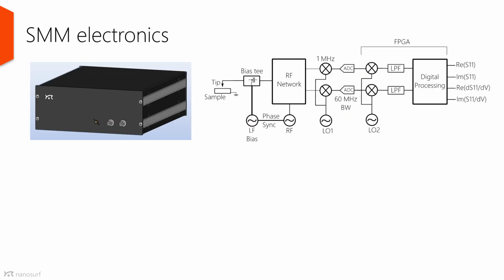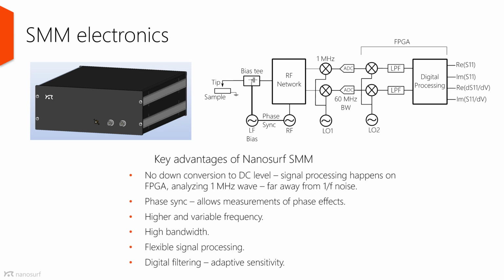For the SMM electronics, we have applied the many years of experience working with microwave technology and rethought the concept of the SMM hardware from the point of view of the lowest noise possible and the highest possible flexibility. We decided to use digital signal processing to work with 1 MHz signals without down conversion to DC level, to avoid 1/f noise. Our RF signal and the low frequency signal are phase synchronous, so you could study the phase effects better. We have a maximum frequency of 6 GHz, and it could be as low as 1 GHz. Because we use digital signal processing, the filtering is already done on the FPGA level and can be adjusted to whatever the scanning speed is for the best signal to noise ratio.